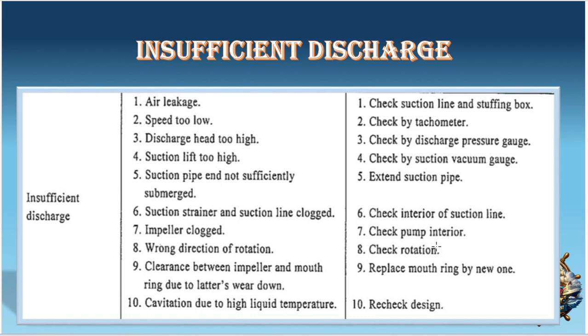Insufficient discharge. Here in this case, we have the discharge, but it is not sufficient. It is insufficient. Then in that case, what will happen? The air leakage is one of the chances. Then again, we have to check from where the air leak is happening, suction line, the stuffing box, whatever, and we have to eliminate that part. The speed is too low. Check with the tachometer and take corrective action. Whatever speed is required, the speed is low. What is the case? Mechanical, electrical, whatever.